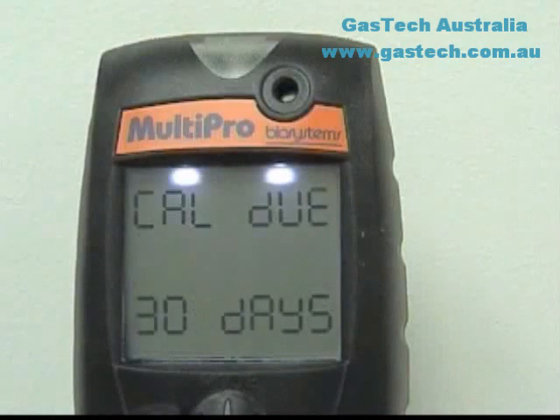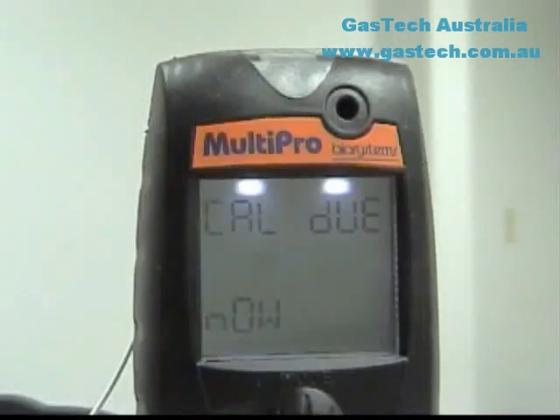After the alarm screens have been displayed, the instrument will show when it is due for calibration. If the instrument is past due for calibration, the screen will display Needs Cal. It will not move on to any further screen until the user acknowledges this message by pressing the mode button.